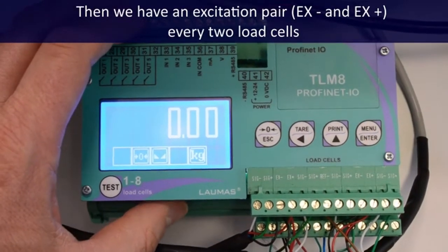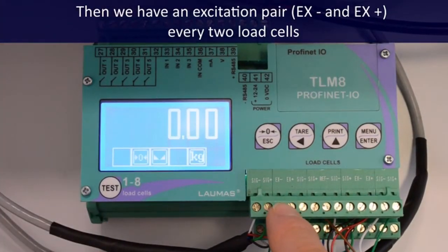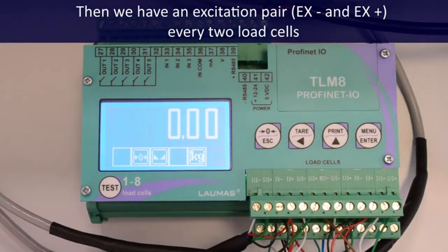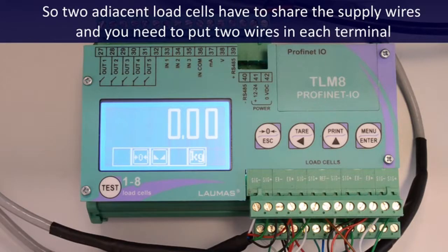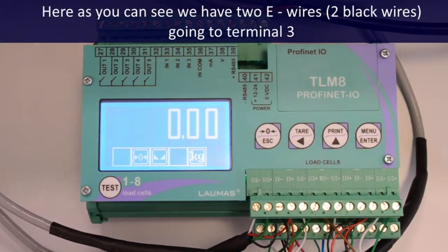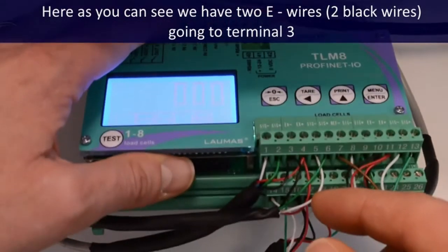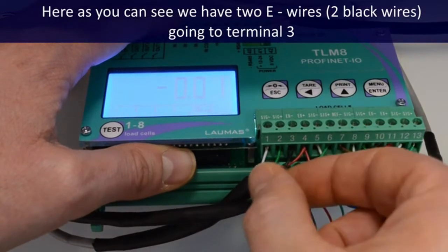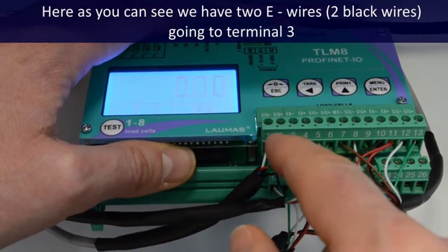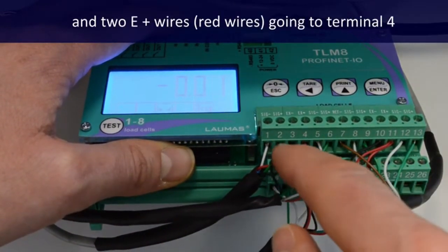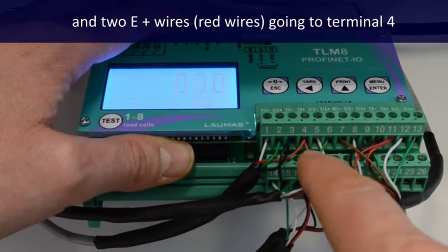Then we have an excitation pair, excitation minus, excitation plus, every 2 load cells. So 2 adjacent load cells have to share the supply wires, and you need to put 2 wires in each terminal. Here, as you can see, we have 2 excitation minus wires, 2 black wires, going to terminal 3, and 2 excitation plus wires, red wires, going to terminal 4.